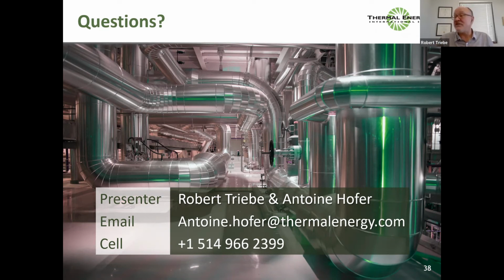Yeah, I'll just stick with the number that you guys saw, which was 800,000 versus 1.2 million, which is 33% less or 50% more, however you'd like to slice it. And we've seen that repeatedly. So there's a company, Boiler Room Equipment. We purchased this company a while ago, and they have actually partnered with Hurst. And Hurst has a skid mounted economizer and hydronic boiler because they also believe in this approach. And so honestly, I would say you're looking at a 35% difference comfortably.